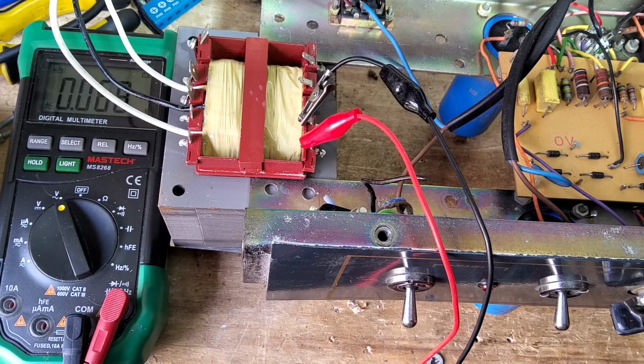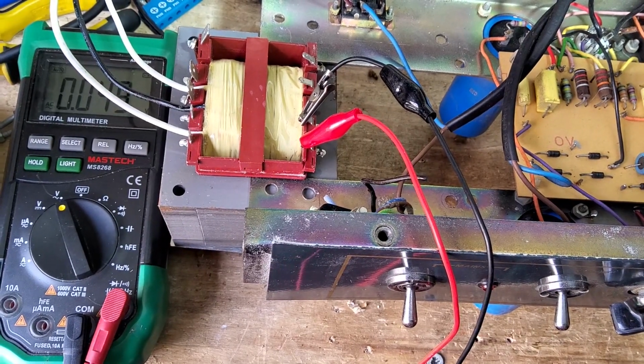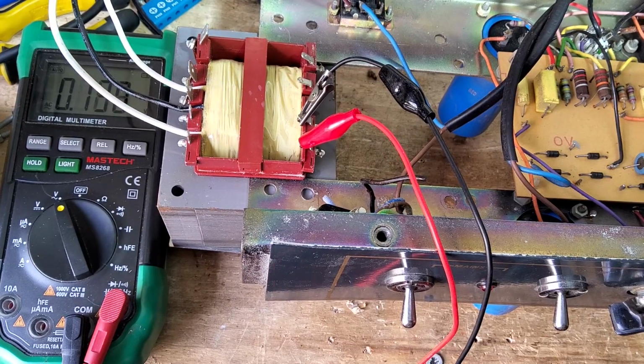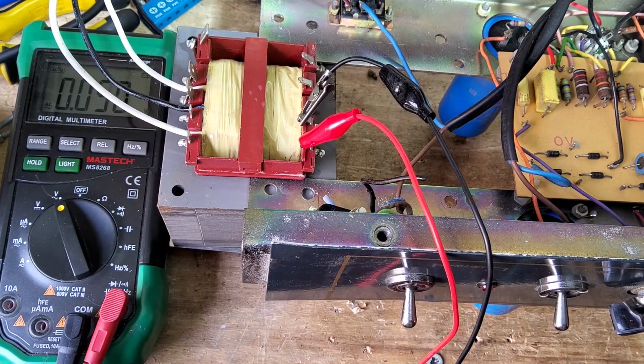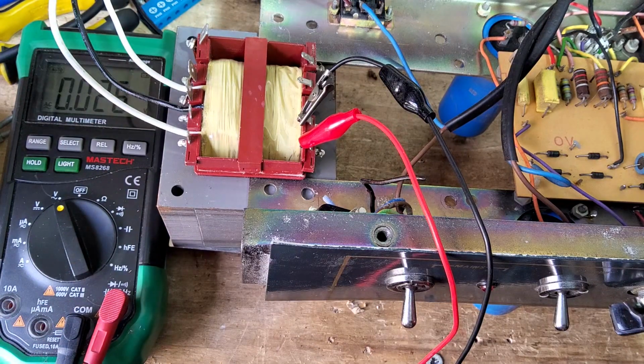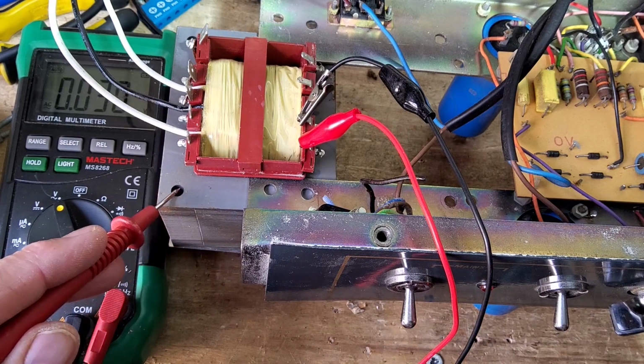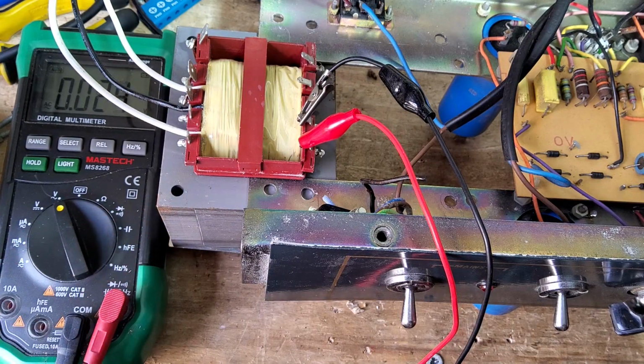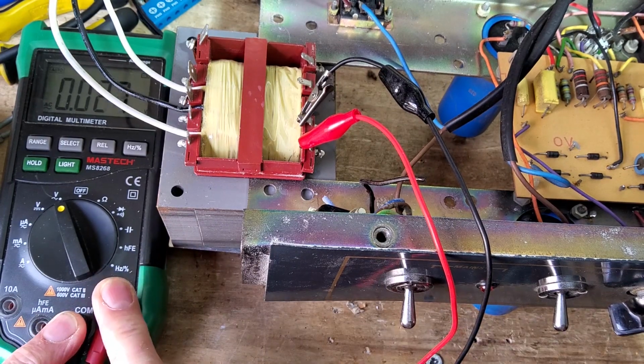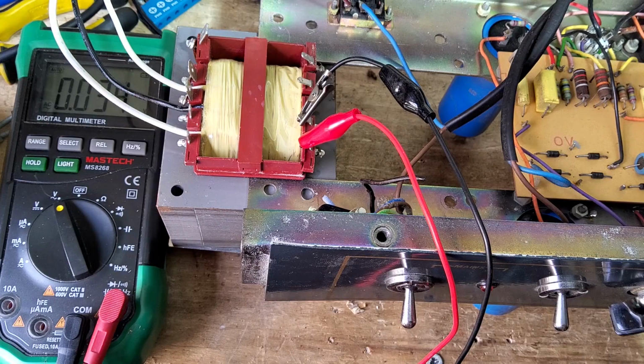So the other good idea when you're doing this is to have an amp meter on the variac, because if you don't know which way you're putting these on, you could be creating a short on these windings. The amp meter will tell you if you suddenly get current on this transformer, even at a low voltage you'll get it as well, then you know straight away to switch off. You can use a current limiter as well.